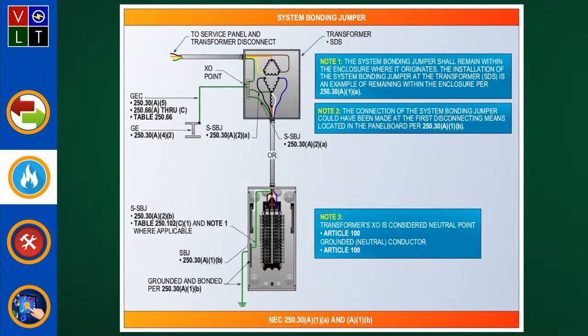I like that. Okay, now the first thing you're going to look at, as I was saying with grounded systems, is the system bonding jumper, in 250.30(A)(1). It says the system bonding jumper, which of course is unspliced, shall be designed and installed based on the ungrounded phase conductor supplying the panelboard, switch, or other equipment, which is connected from the secondary side of that transformer.